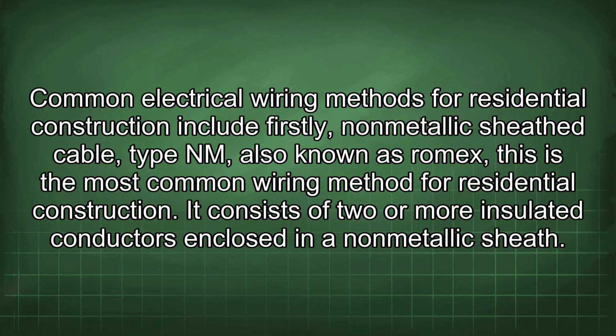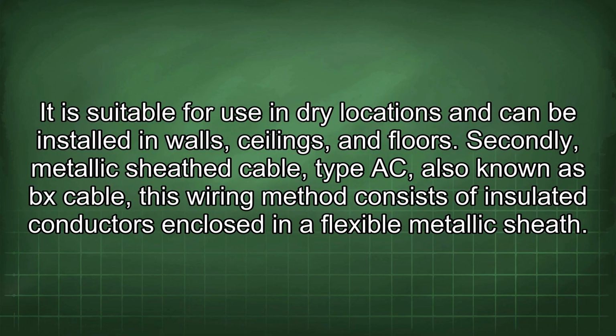Common electrical wiring methods for residential construction include, firstly, non-metallic sheath cable, type NM, also known as Romex. This is the most common wiring method for residential construction. It consists of two or more insulated conductors enclosed in a non-metallic sheath. It is suitable for use in dry locations and can be installed in walls, ceilings, and floors.